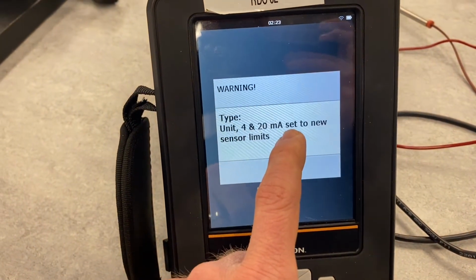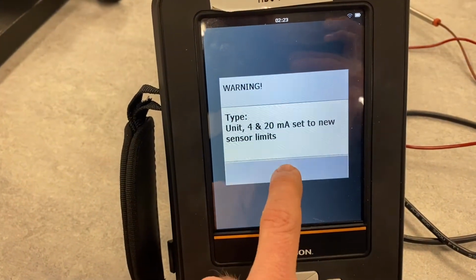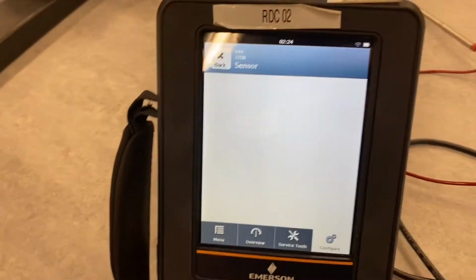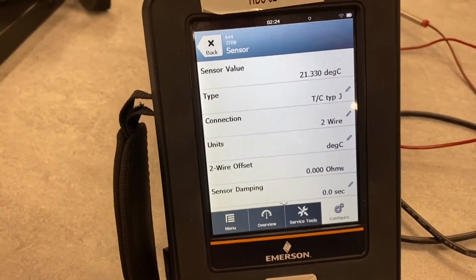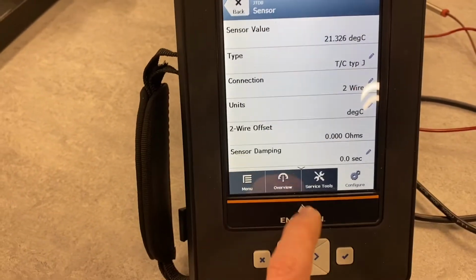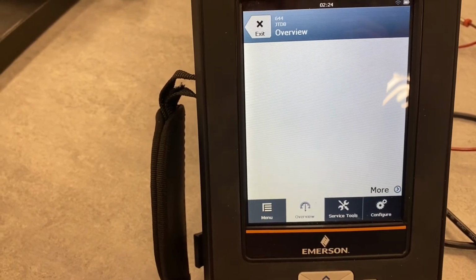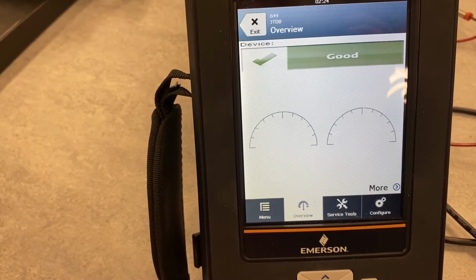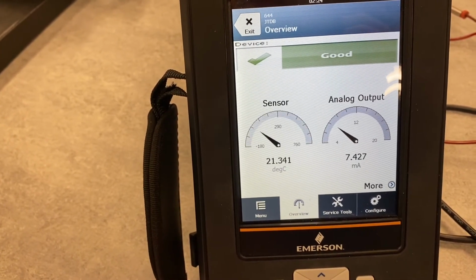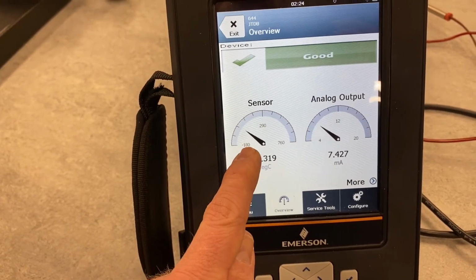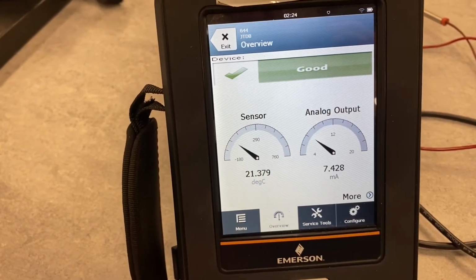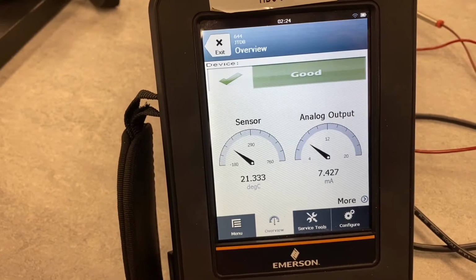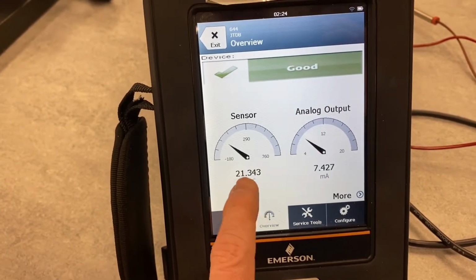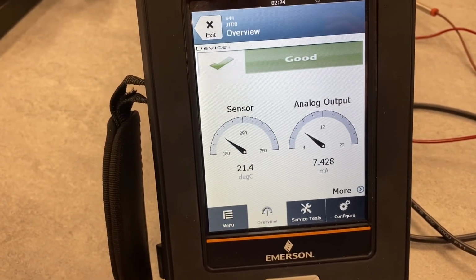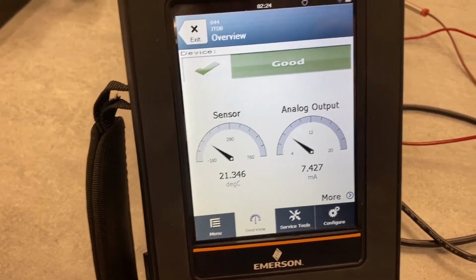Unit 4 to 20 milliamp set to new sensor limits, click OK. So what that's saying is the 4 to 20 milliamp output is set to the sensor limits, which is a really large range. We'll probably see it right here. Yes, minus 180 degrees C to positive 760. So that's what the 4 to 20 milliamp signal is set to. You can see right now it's measuring room temperature, right around 21.4 degrees C.